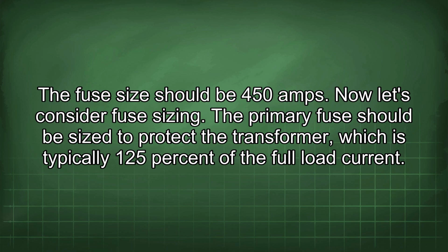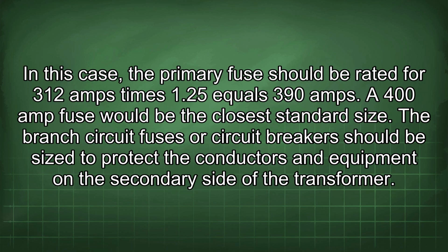Now let's consider fuse sizing. The primary fuse should be sized to protect the transformer, which is typically 125% of the full load current. In this case, the primary fuse should be rated for 312 amps times 1.25 equals 390 amps. A 400 amp fuse would be the closest standard size.